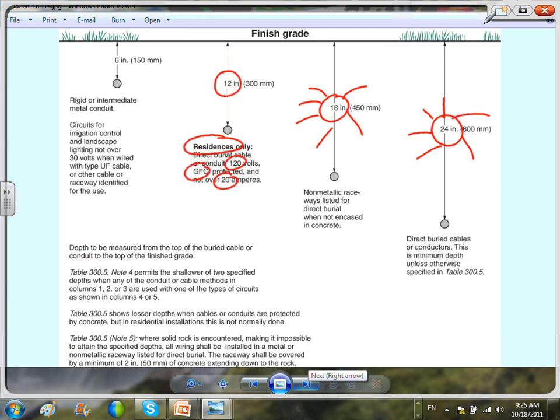Yeah, you talk about direct buried. Now, of course, if you direct bury a cable, you're not going to put big rocks right on top of the cable. You have to put some sand around the cable. What we do, guys, if it's rocky, direct buried cable, you put your cable and then you put some sand or soil, not sharp objects, right around the cable. Then you can put your rocks. They don't want you to put sharp rocks right on top of a cable because it cuts through the cable as you bury it. Is that what you were after? Yeah, I was just talking about that.